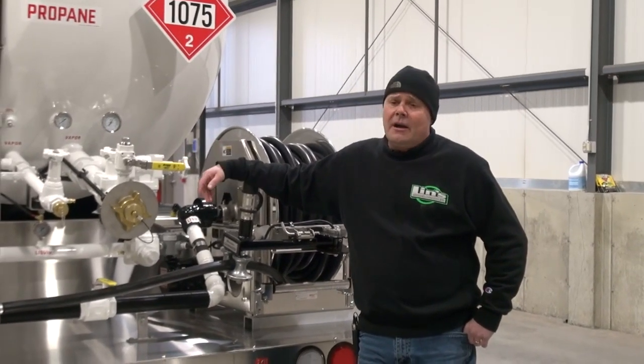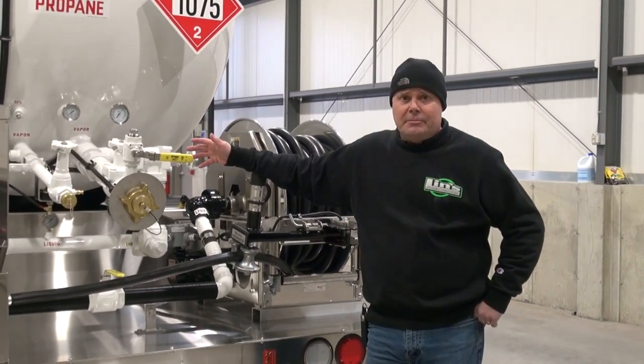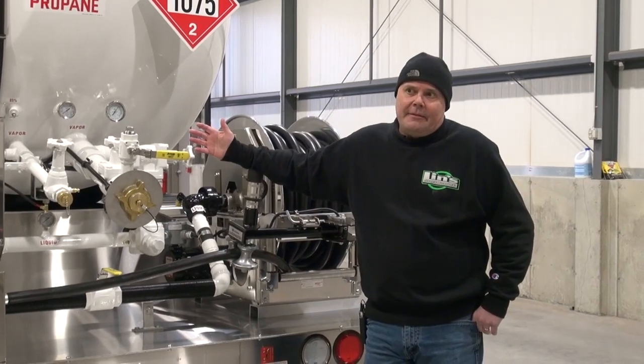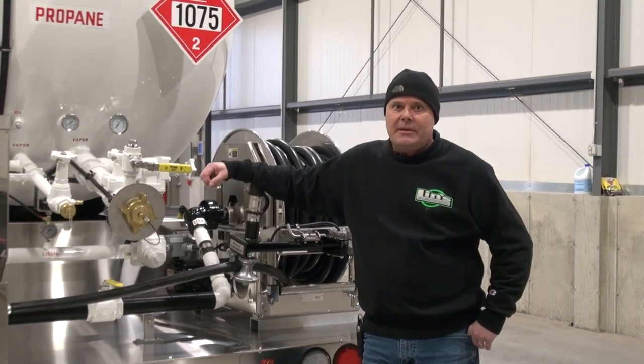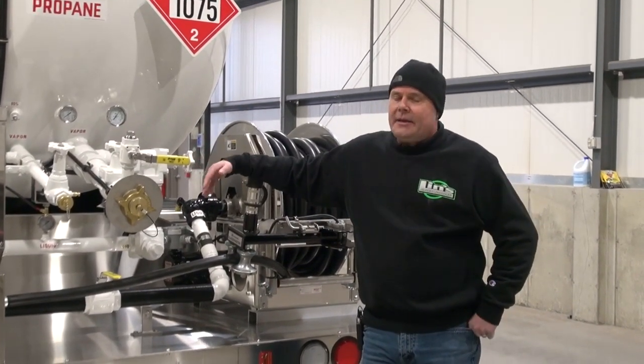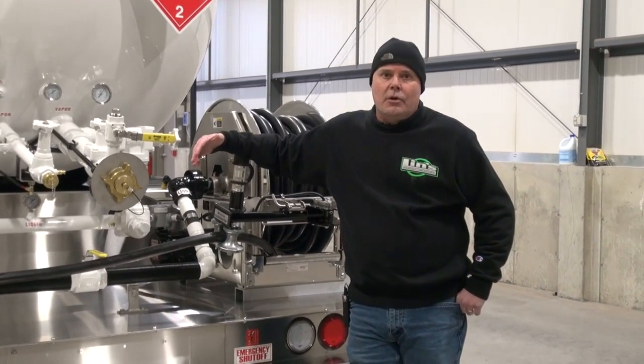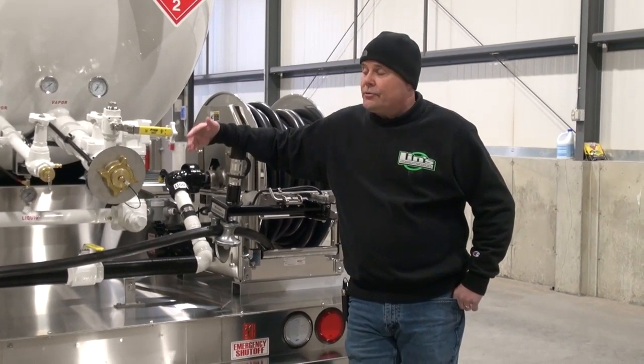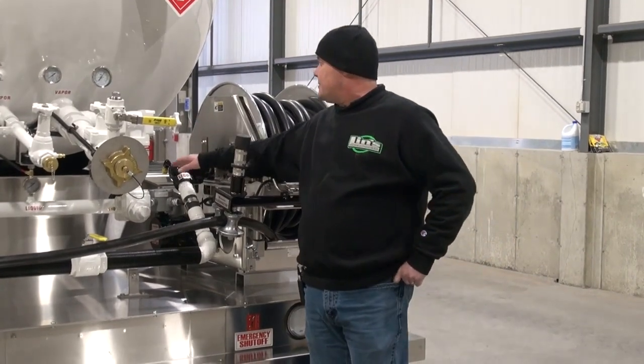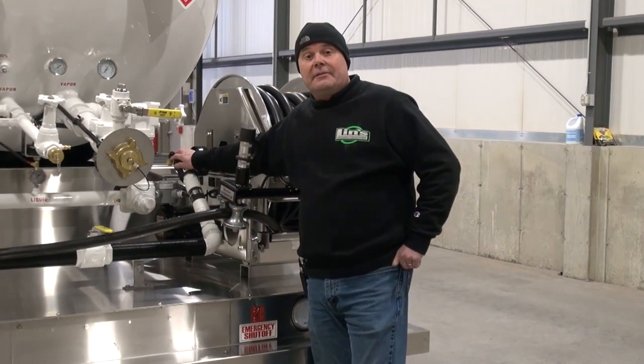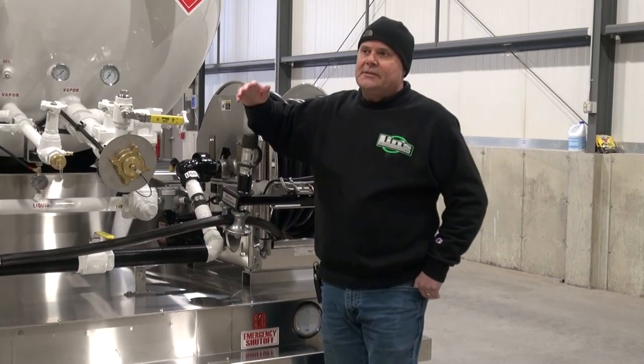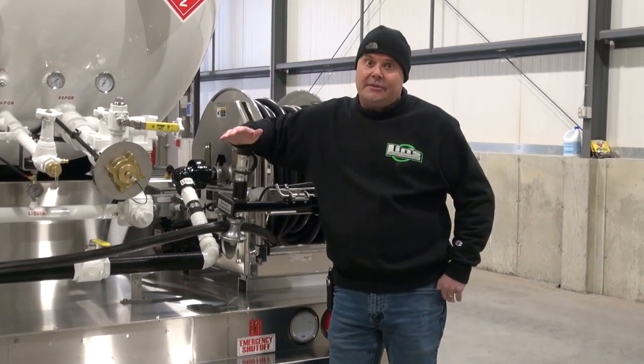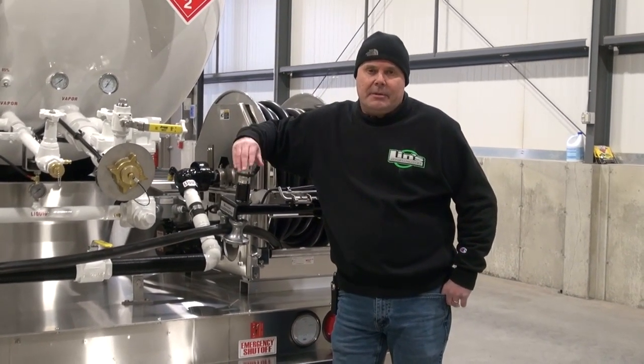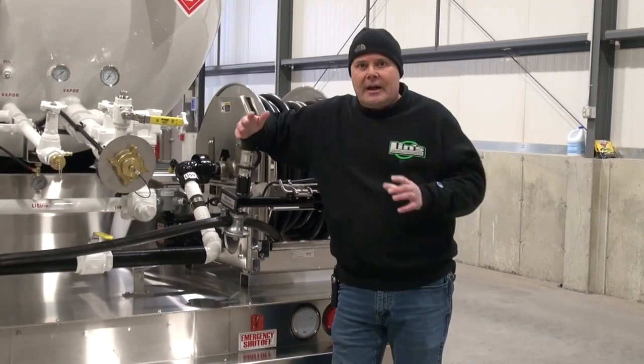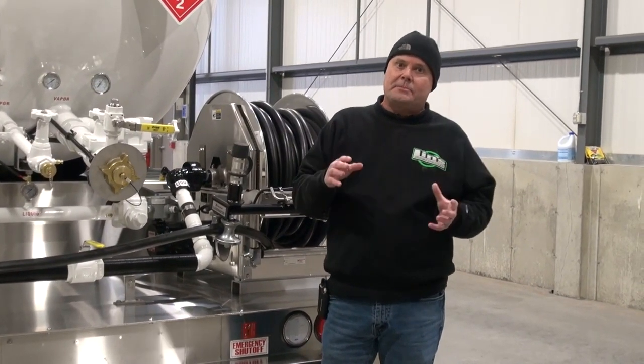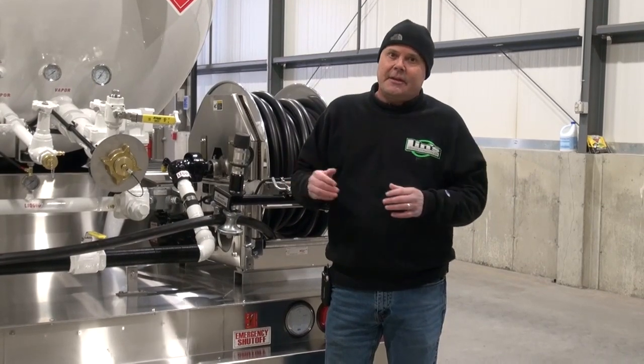Add to that 100 PSI from the pump differential pressure, and you're pumping at 265, 275 PSI. When you're that high, it is possible that when you shut the hose end nozzle after delivery, you could have a spike and get a brief release from the 450 PSI relief valve. We see this in the summer months on trucks that aren't running heat exchangers, so it's definitely a possibility. And that's why we recommend isolating it between June 1st and September 1st, and at the very least, during hot spells or heat waves.